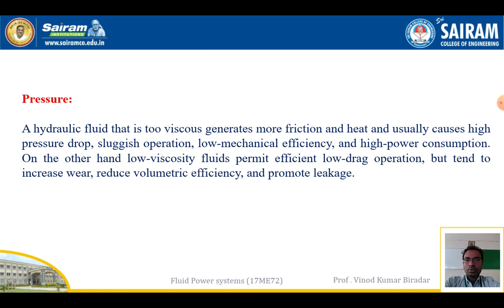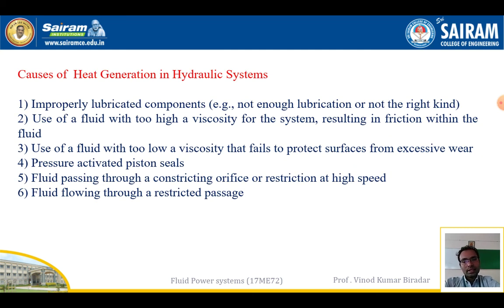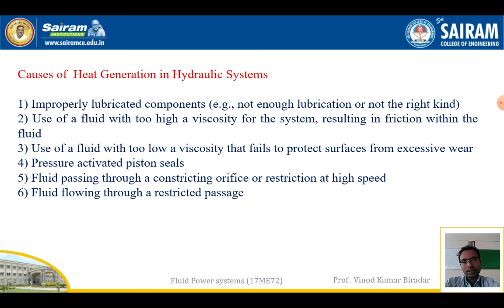The main causes of heat generation in a hydraulic power system are as follows. First, improperly lubricated components — components not assembled in proper fashion — cause heat generation due to insufficient or incorrect lubrication. Second, use of fluid with too high a viscosity results in friction within the fluid. Third, use of fluid with too low a viscosity fails to protect the surfaces from wear. Fourth, a pressure-activated piston seal may also cause heat generation.